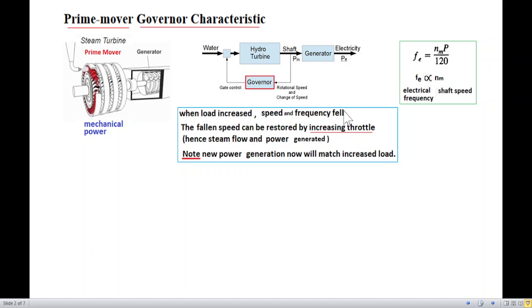And here is another explanation. When load increases, speed and frequency fall down. The fallen speed can be restored by increasing throttle, the steam flow and the power generated. And once we have done this, we have increased the new power generation. Now, we'll match the increased load. And that is what we are going to see in the example.